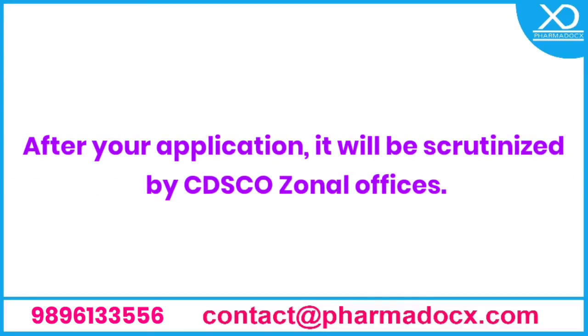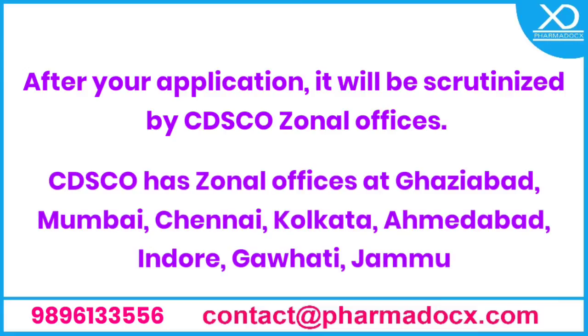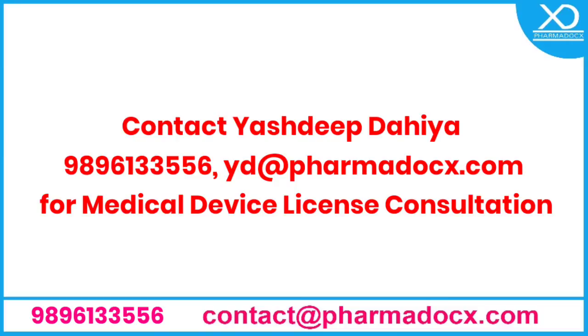Your application will then be scrutinized by the zonal offices of CDSCO. CDSCO has zonal offices at various locations, mainly at Ghaziabad, Mumbai, Chennai, Kolkata, Ahmedabad, Indore, Guwahati, Jammu, Baddi, etc. So whichever zone you fall under, they will conduct your audit.